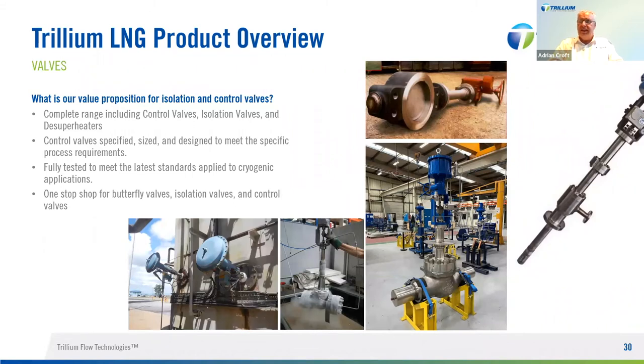We'll touch on a separate slide on desuperheaters, but essentially on cryogenic control valves, and many cryogenic valves for that matter, there is quite often a requirement from the customer to fully test them. And we do that in a bath of liquid nitrogen. Again, specifications vary, but as we dip the valves into the liquid nitrogen, we pump helium through the valve, measure any leakage that takes place through the valve, and also make sure the valve will functionally operate after it's been cooled. The picture on the left is some cold box valves. Ironically, although it's a cold box, it's located in Bermuda.